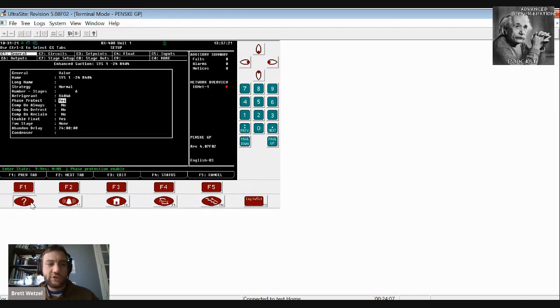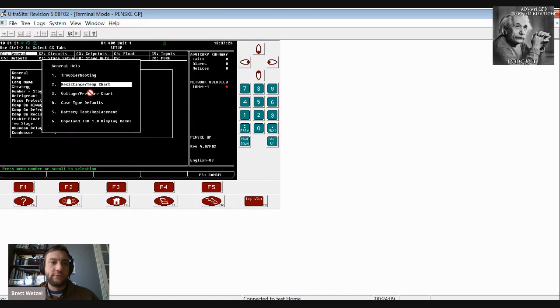Shift question mark again - you can do voltage chart, and basically remember with transducers, they induce a voltage back to the board to tell it what pressure it is. So if you have a 100-pound pressure transducer, and it goes all the way up to 100, technically from 0.5 to 4.5 is your range here. So at 2.5, a 100-pound pressure transducer should be outputting 50 psi, and so on and so forth with a 200-pound, 500-pound.